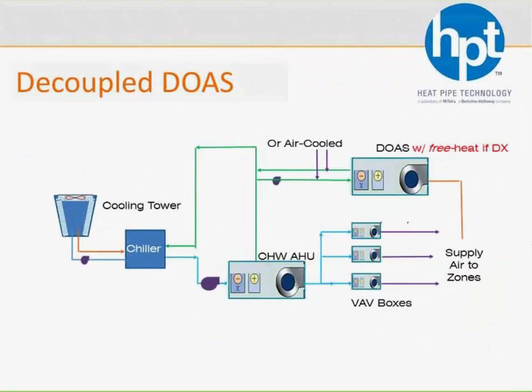So here, conversely, is the decoupled dedicated outside air system. Decoupled because now, instead of mixing the outside air with the return air upstream of one cooling coil, you're actually separating or decoupling the two. So you have an air handler or a DOAS unit that is strictly handling ventilation air. Then you have separate air handlers for recirculation or handling all return air.